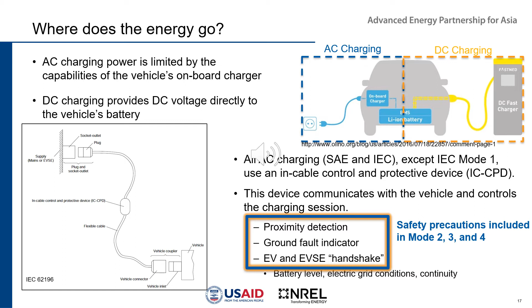In addition to the vehicle connections, it's also important to understand how the EVSE interacts with the electric grid. This environment between the grid and EVSE is typically detailed in installation codes. For the United States, the National Electric Code, Section 625, details specific requirements for the installation of EVSE. The most important of which is probably the branch circuit requirements, where each permanently installed EVSE must be supplied by an individual branch circuit with a single circuit breaker designed for overcurrent protection.